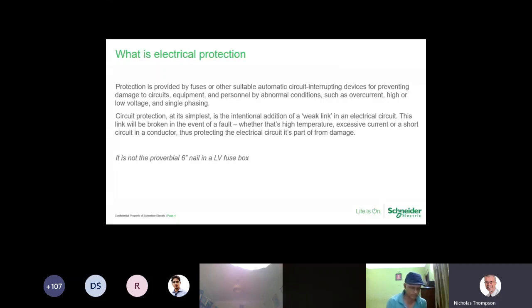But essentially, whatever we're using as protection, it is the deliberate weak link. And that weak link is designed to operate before something else potentially fails, and that potential failure may be catastrophic. We always say that swapping out a piece of fuse wire for a 6-inch nail is not the best form of protection. A 6-inch nail will take many thousands of amps to actually melt it, so it's literally adding another big link in the chain.